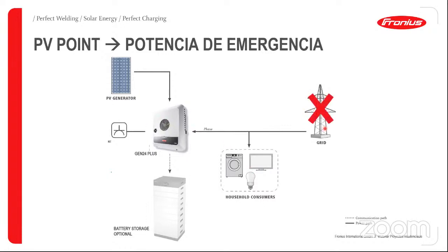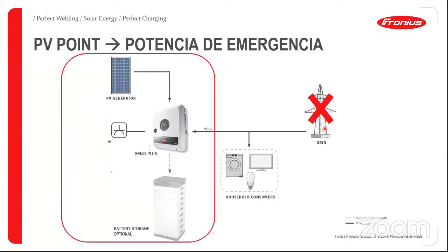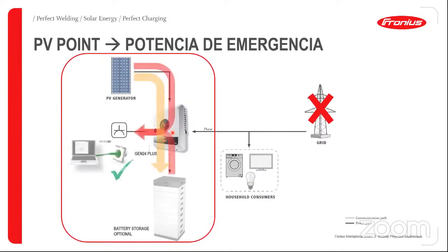If the grid fails, if we have a blackout or something happens with the grid, we also know the anti-islanding program in the inverter doesn't allow the system to inject into the grid. But this inverter has a second circuit, a different circuit from which we can connect different devices in our house. We can connect critical loads to this point, and from the power that is being produced in the modules, we can connect devices like a laptop or a small fridge or something that is needed in the installation, and the inverter can continue delivering some power.